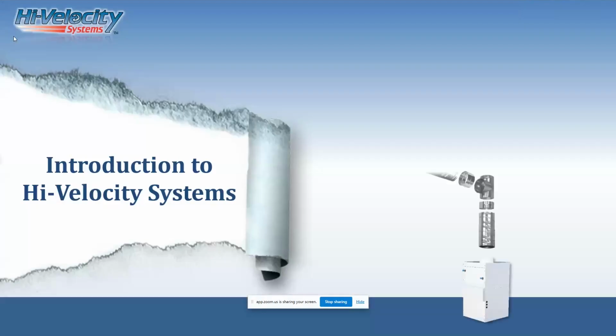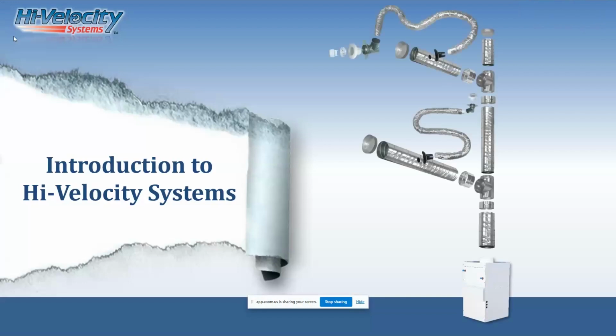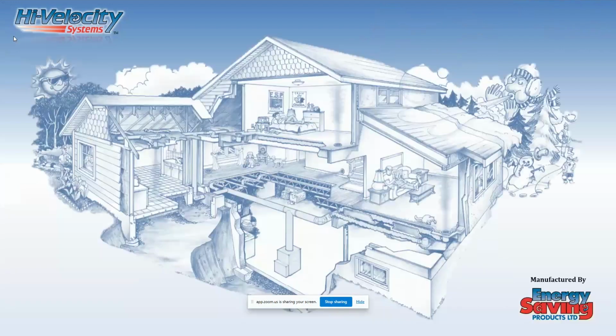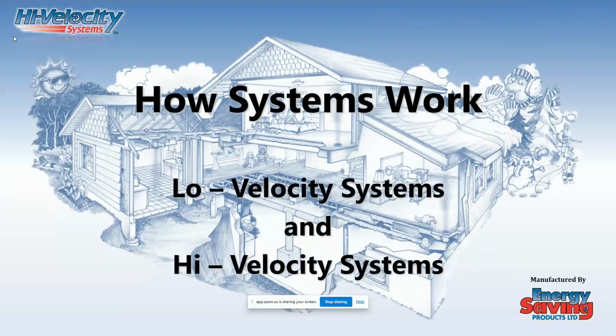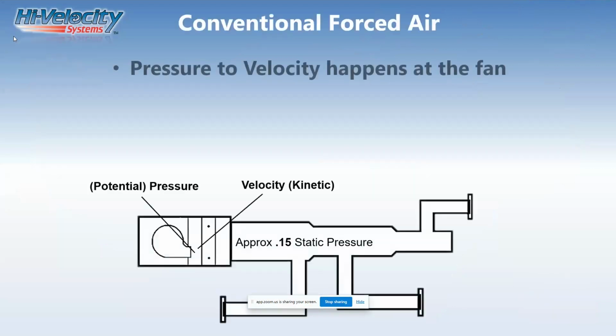Again, we're noted for high velocity systems. It's a smaller duct. An introduction to high velocity, well, you can notice on the screen that typically our ductwork is smaller when we talk about high velocity. So very, very unique that way. How the system works, well, I'm going to talk about low velocity, I'm going to talk about high velocity, and I'm also going to fill in the gaps that both Jordan and Dawn talked about.